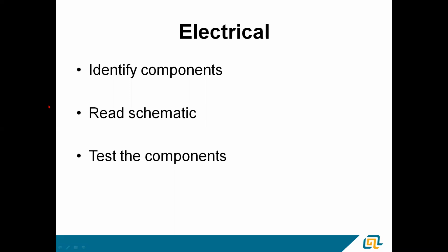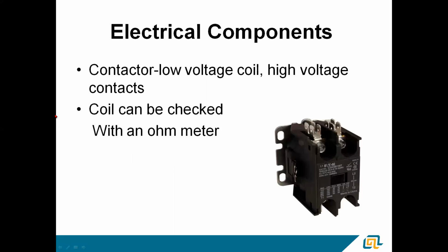On the electrical side, we're going to look at a couple of electrical components. Got to touch on a couple of schematics, nothing major, and look at how to test components. Contactor, one of our most common ones, low voltage coil, high voltage contacts. Check them with an ohm meter. Typical contactors that I've checked over my career, I'm seeing usually between 20, 30 ohms on that 24 volt coil.